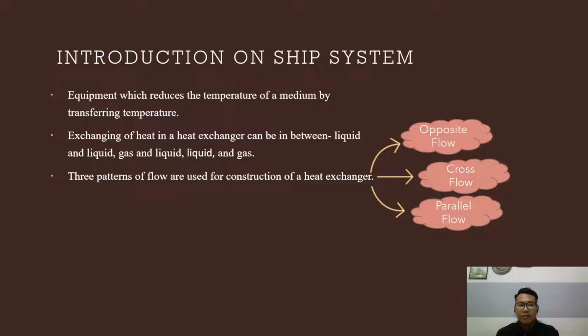Opposite flow is where the primary medium and the secondary medium, which is cooling the primary medium, enter the heat exchanger in the opposite direction to each other. For the cross flow, the primary and secondary medium enter the exchanger perpendicular to each other. Parallel flow is where the primary and secondary medium both enter the heat exchanger parallel to each other.